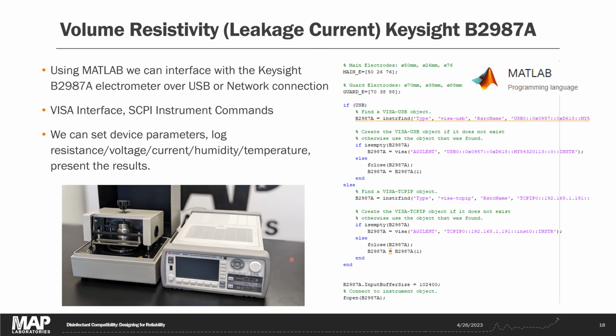Running ASTM D257 requires some specific instrumentation. In our case, we're using a Keysight B2987A electrometer, which is capable of delivering up to 1000 volts DC using its internal power supply. The method calls for 500 volts, so we're able to do double that. You also need to be able to measure very small currents. This electrometer can measure electrical currents as small as, I believe the rated resolution is 0.01 femtoamps. A femtoamp is 10 to the minus 15 amps, so that's something like 62 electrons per second is the resolution spec on this electrometer.